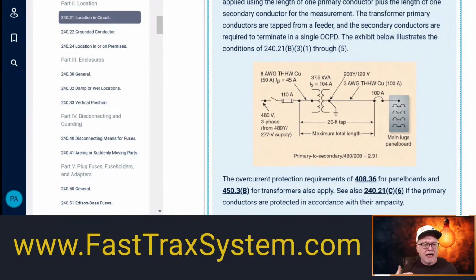And we divide that by 480, multiplied by the square root of 3. That gave us the 831.36, right? So let's do that. So let's take 37.5, and we're going to divide that by 831.36. And that gives us 45.10. Okay. All right. So here the amps are 45.10. Okay. So that's what we have on this.